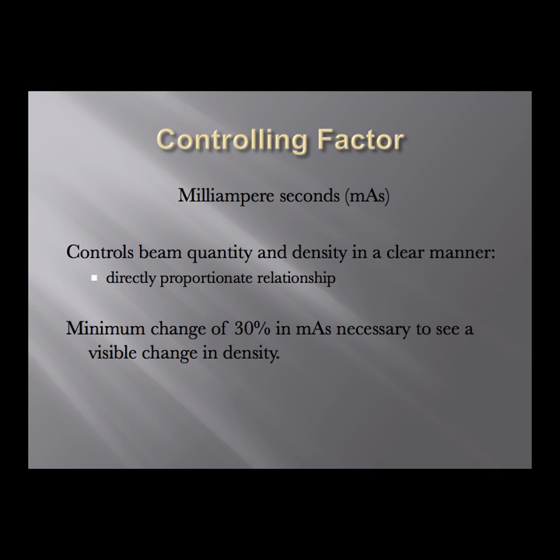mAs controls beam quantity, all leading back to the process of thermionic emission and the quantity of electrons boiled off at the cathode, which in turn control the quantity of x-ray photons produced at the anode. As mAs goes up, we're heating the filament to a higher degree, boiling off more electrons, and they in turn are converted into more x-ray photons. This is a pretty directly proportionate relationship, though your textbook notes it's not exactly doubling or halving.